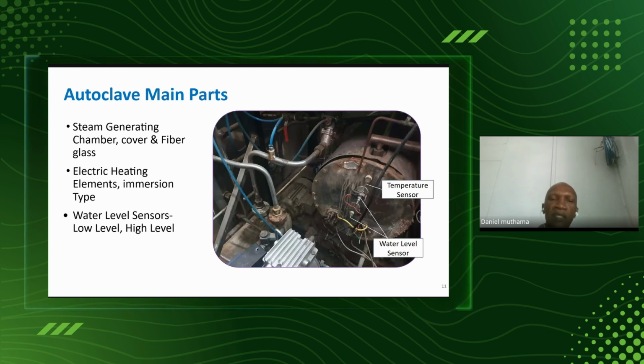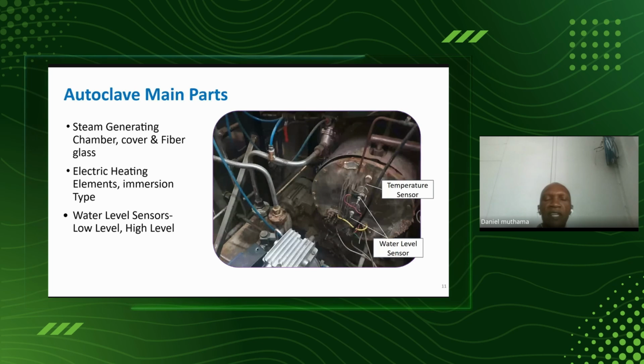But if you find this is measuring 80 ohms, this is measuring 80 ohms, this one is measuring maybe 200 ohms, more than these two, it means this element has a problem and this one has to be replaced. So what we mean here, for you to be able to get the right amount of heat, this set and this set, all the electric heating elements must be providing the correct heat.